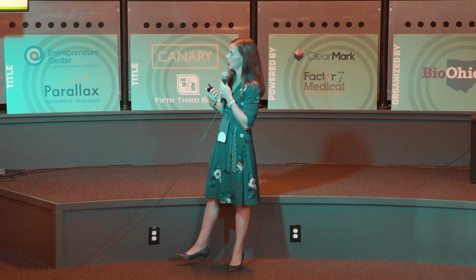So what I've listed here is, a Class 1 device doesn't have to go through Premarket. Usually there are some exemptions. You're looking at $250,000 to $1 million, and it's really dependent on the complexity, what this device entails, what kind of testing goes into this type of device. Class 2, you're looking at 12 to 24 months, generally speaking, and this could be $500,000 to well over $1 million. And again, with the variety of devices in the Class 2 space, it could be a rather complex instrumentation, or it could be a navigation system for vascular surgery. The difference between the two is pretty substantial, but they do fall in the same classification. So you're looking at least $500,000 to $1 million plus at that stage.